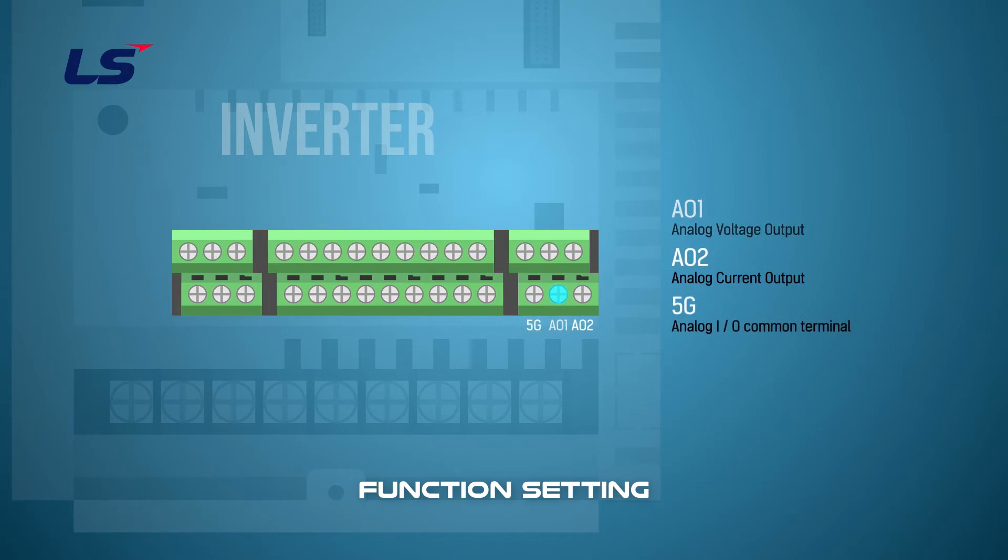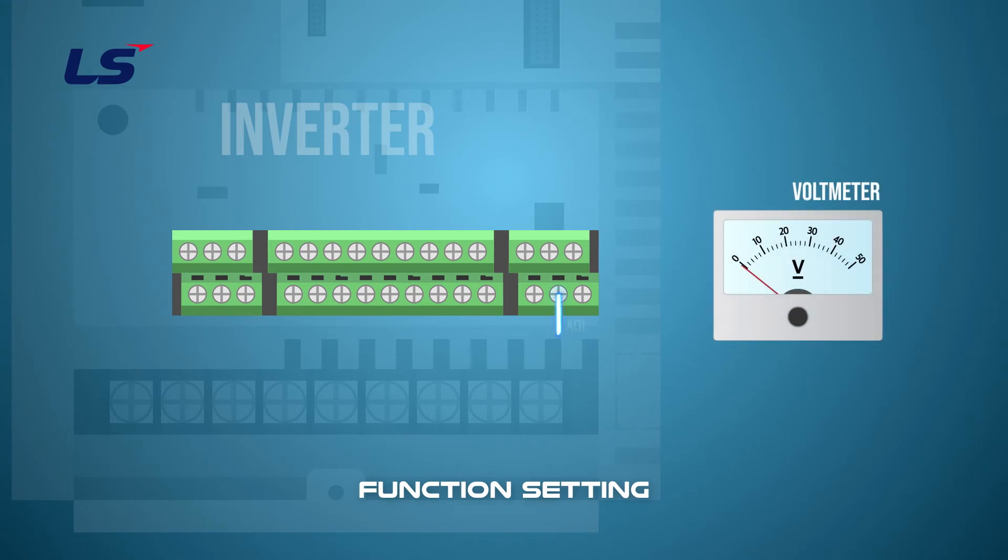AO1 is the analog voltage output terminal from 0 to 10 volts. AO2 is the analog current output terminal from 0 to 20 milliamps. And 5G is the analog input and output common terminal. To output voltage to the voltmeter, you can connect the two terminals AO1 and 5G.